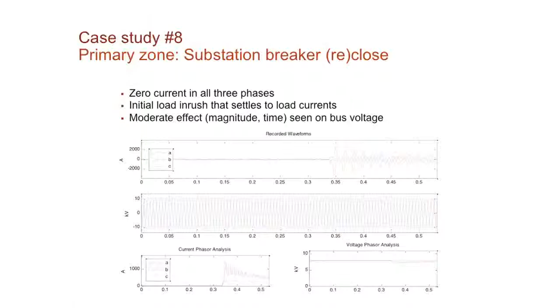Here's a substation reclose, and here's the case where you do see the inrush, and then it does settle back down to load currents. So there's some very interesting information there. Moderate effect on the bus voltage, so you can see how it's affecting the bus in the substation based on that. And again, it was on a close because there was zero current before this event.